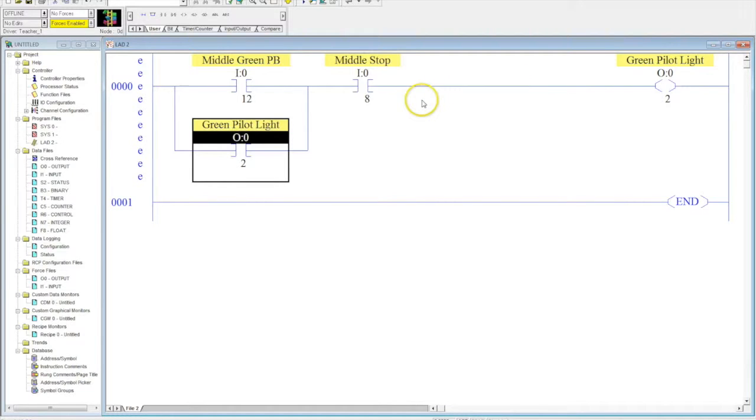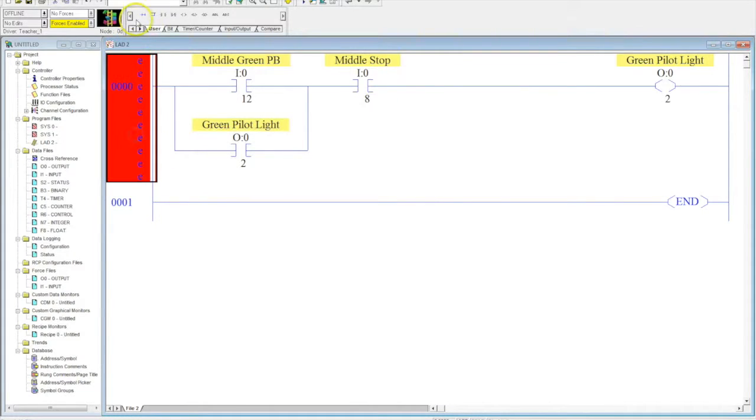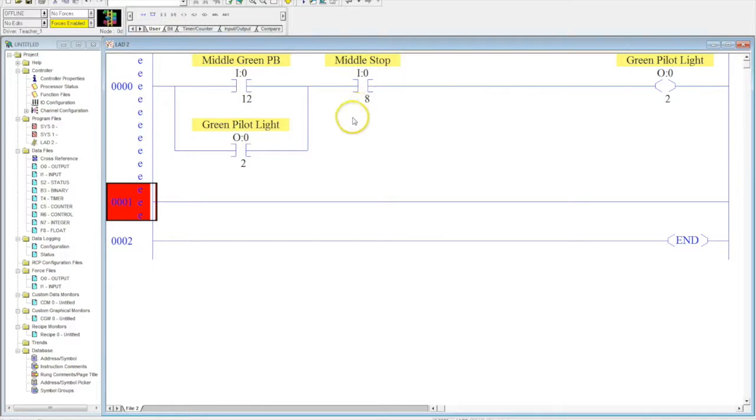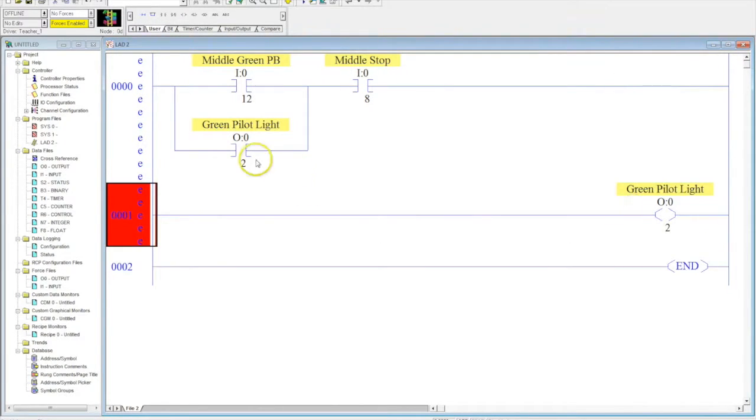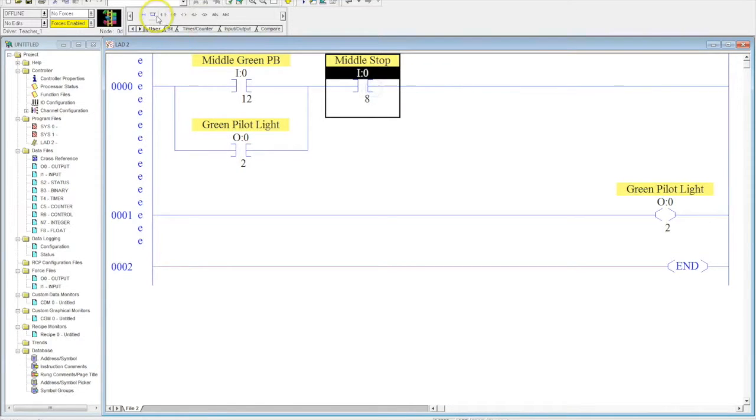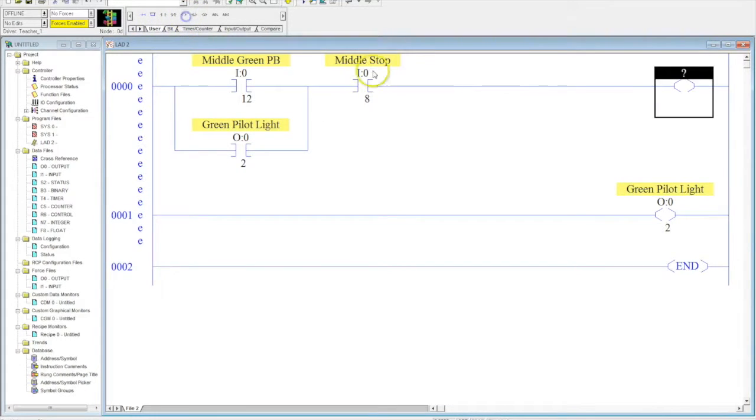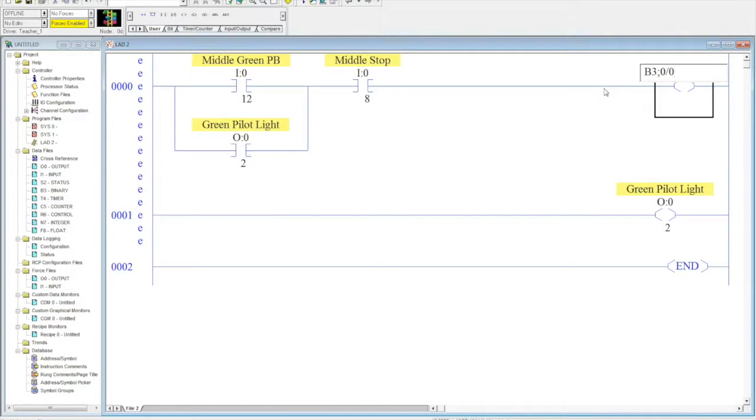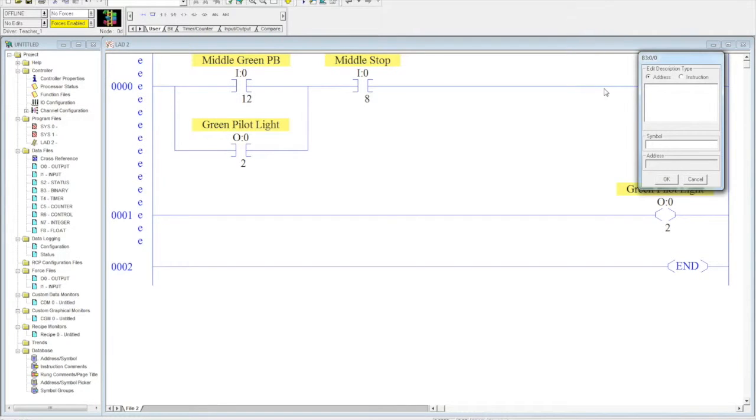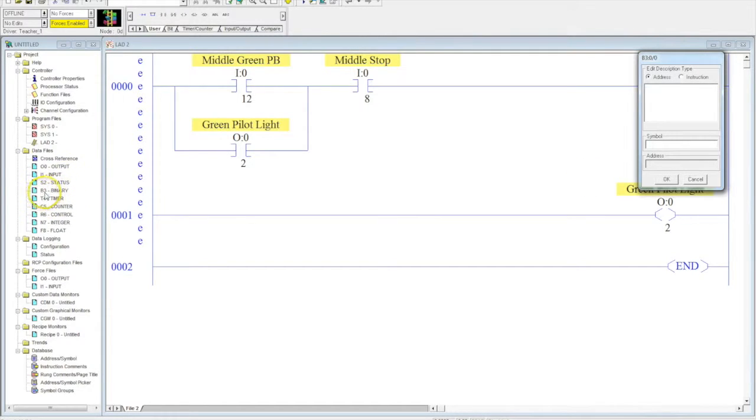Another way to accomplish this same circuit is to use what's called a B3, also known as the internal relay. If you wanted to use a B3, you would take this output, drop it down to here, and then you would put a new output over here. You're going to type B3 colon zero forward slash zero. You start to address this just like an output, but instead of putting an O in front, you put a B3. The B stands for binary, and the three stands for what folder it's in, and that's actually located right here, B3 dash binary.